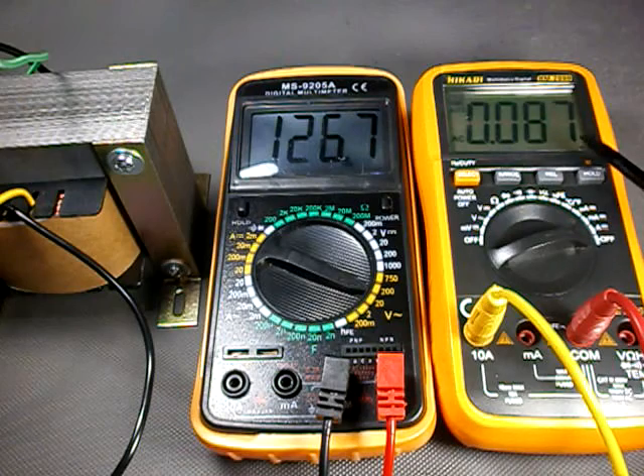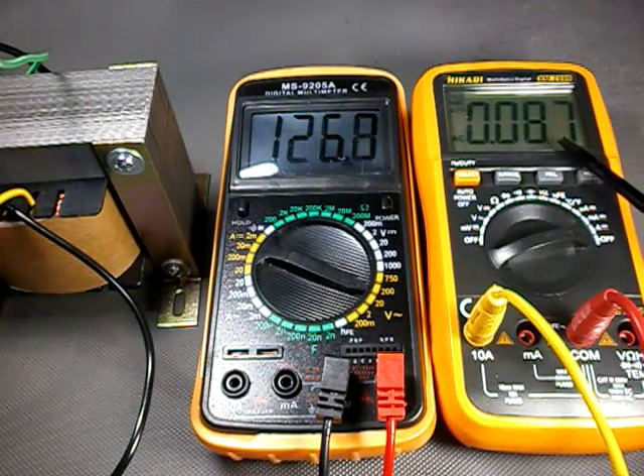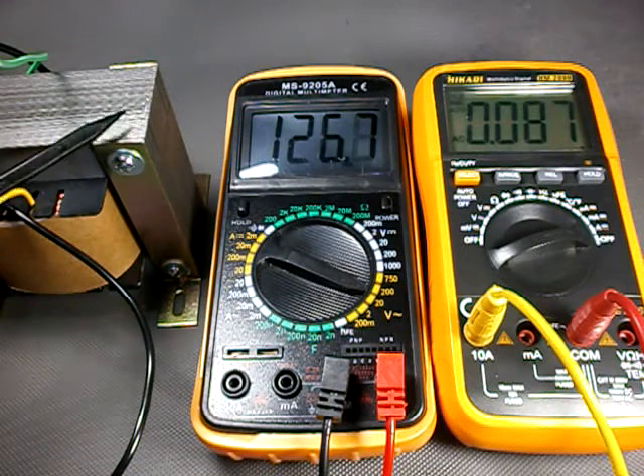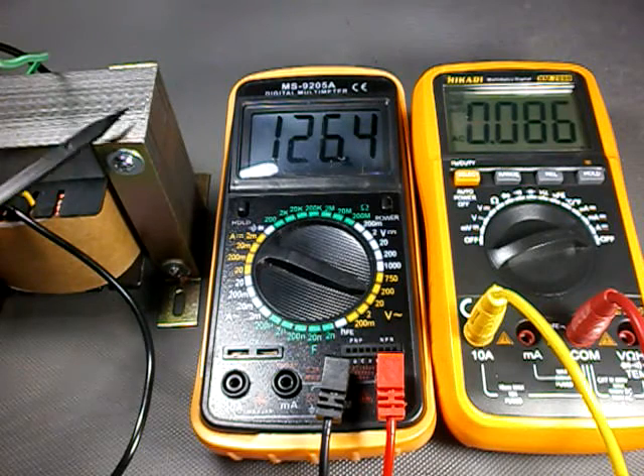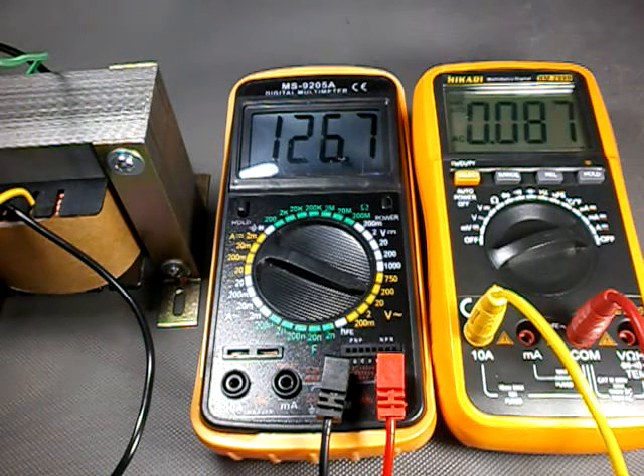The magnetizing current plus the core loss current that comprise the idle current is 87 milliamperes, which is a very good figure. Since there is no current in the secondary and the idle current is much less than the nominal current, the effect of R sub W and L sub Lk can be neglected for this test. This test also indicates if there is a shorted turn in any of the windings. If that is the case, the current on the primary will be only limited by the resistance of the primary winding and will certainly be greater than the nominal current for which the transformer has been designed.